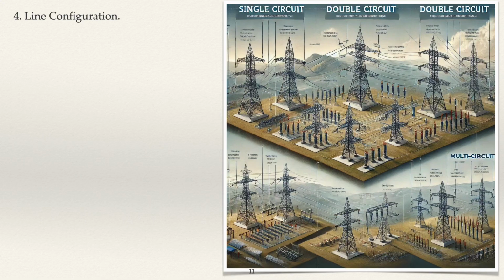7. Clearances. Phase-to-phase clearance ensures no electrical faults occur due to close proximity between conductors. Phase-to-ground clearance maintains a safe distance between conductors and the ground to prevent arcing and ensure public safety. 8. Tower design impact. Line configuration affects the design of transmission towers, including their height, weight, and load-carrying capacity. Towers must accommodate the spacing, arrangement, and weight of conductors while maintaining structural stability.